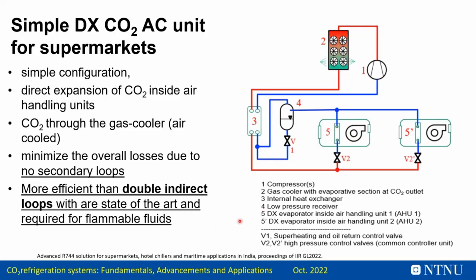If we have a traditional chiller, the chiller first cools water, the water goes into the air handling units, and it comes back at 12 degrees C, and it's supplied at 7 or something like that. On the other side of the chiller, mainly we have evaporative cooling or a secondary loop towards a dry cooler, which is the other indirect loop.